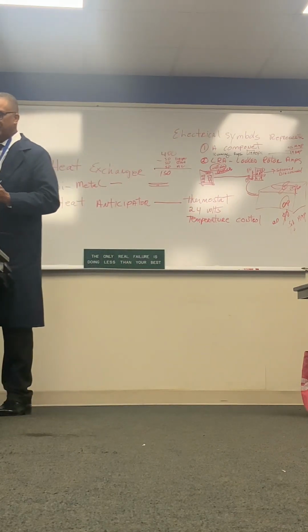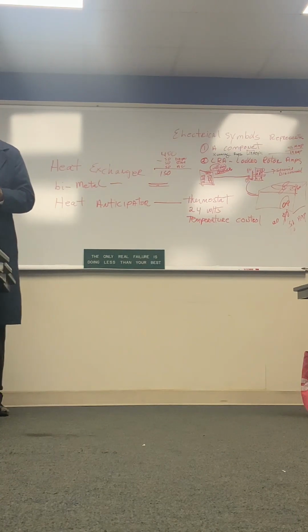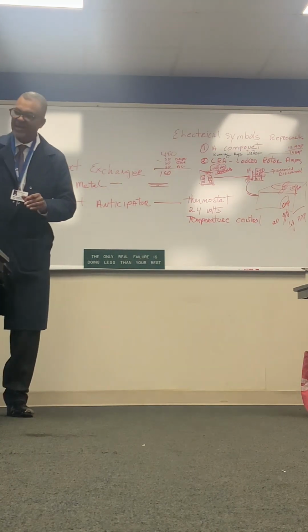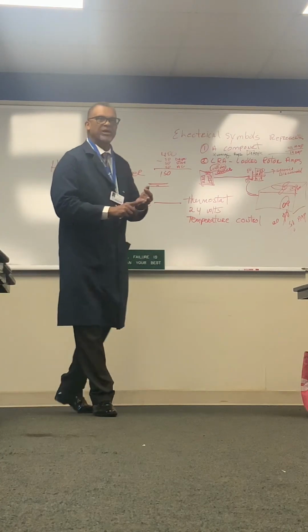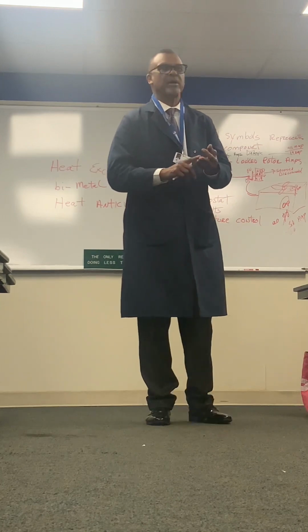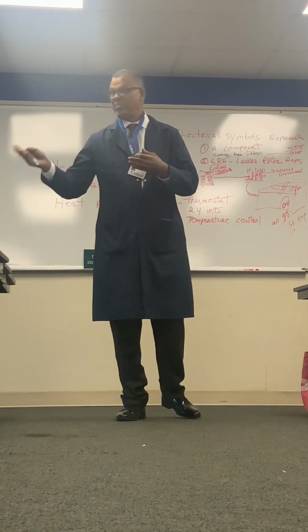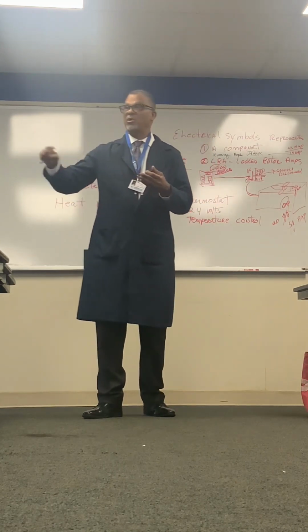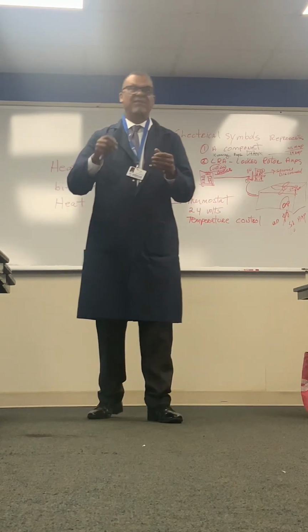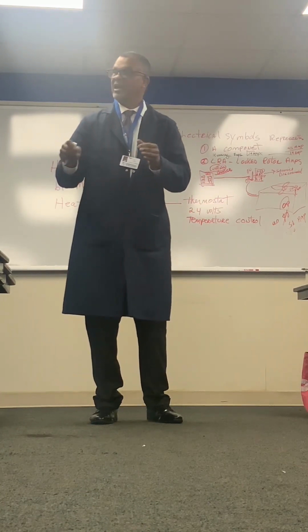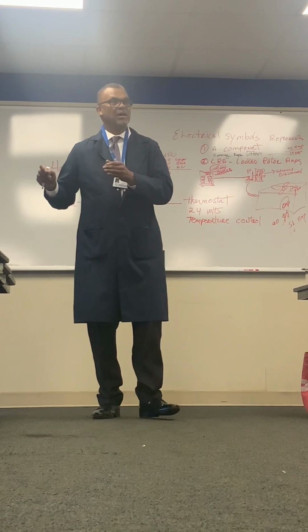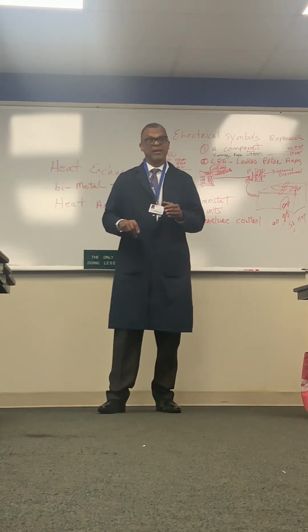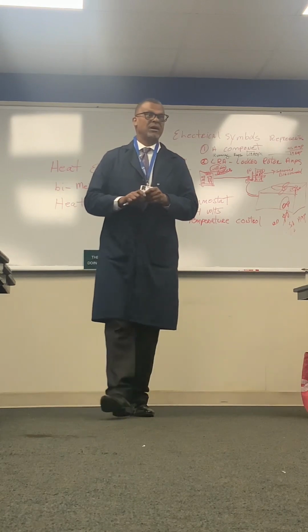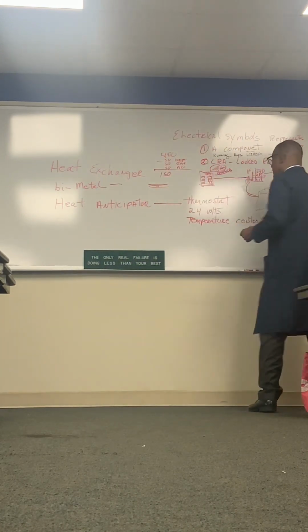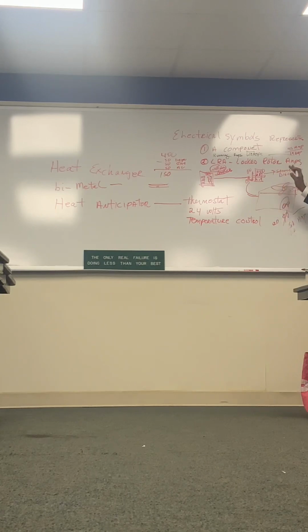That's why we break down components into what they are. Oh, that's a motor. How does it work? How do we validate how it works? Amperage, voltage, lock rotor, running rotor, whatever it takes, RPMs for a motor, it tells you rotations per minute. Indoor fan is going to have a different RPM rotation than an outdoor fan. We're moving way more air outside, probably 5 times more air outside across this unit, because there's heat out here. And if we don't get rid of the heat from that unit, we can't cool.